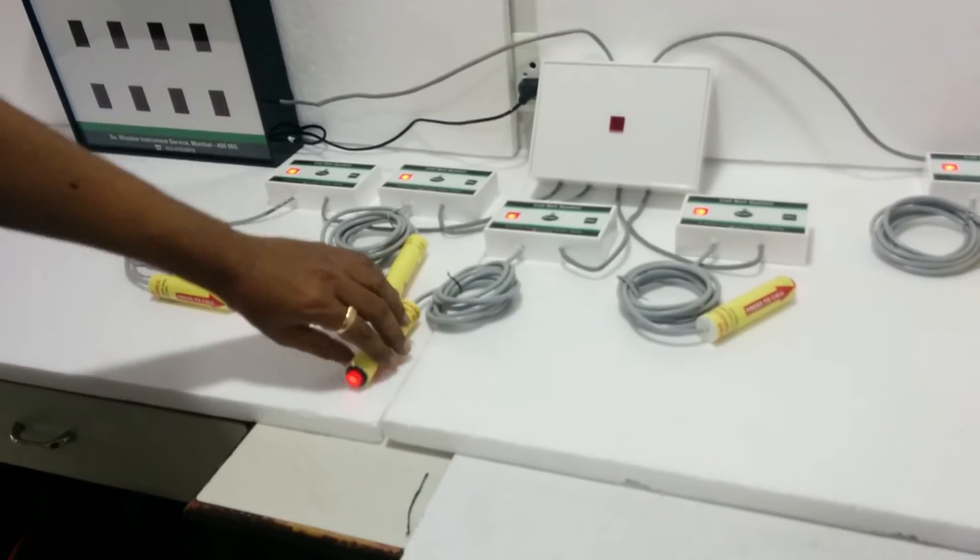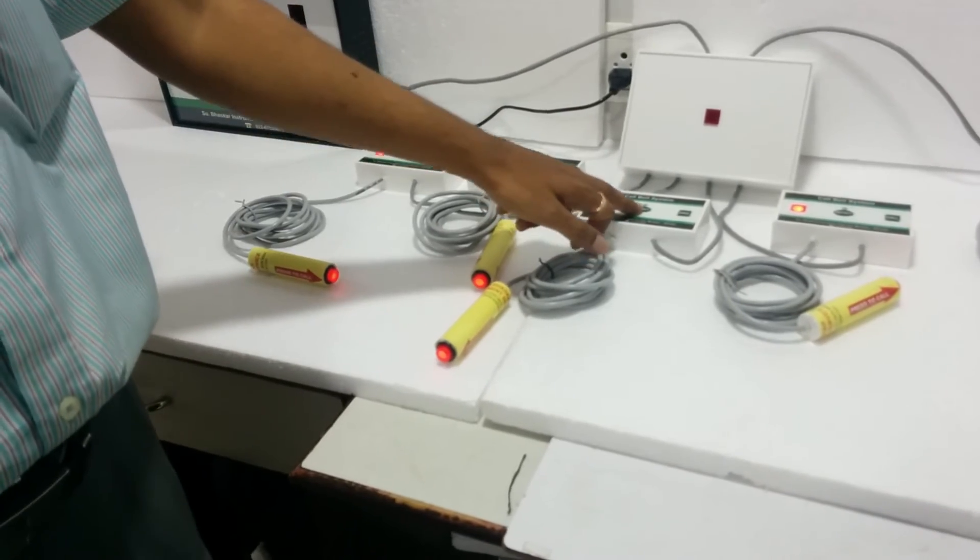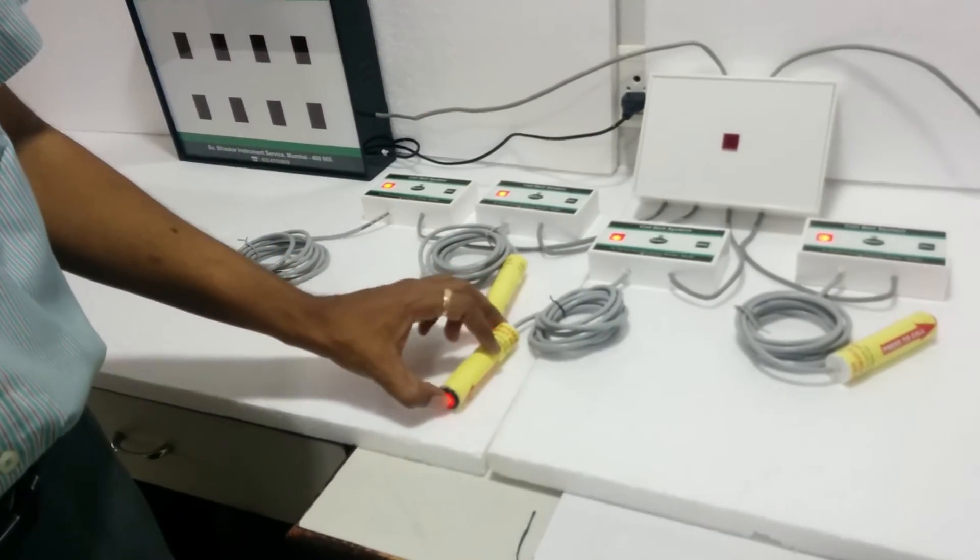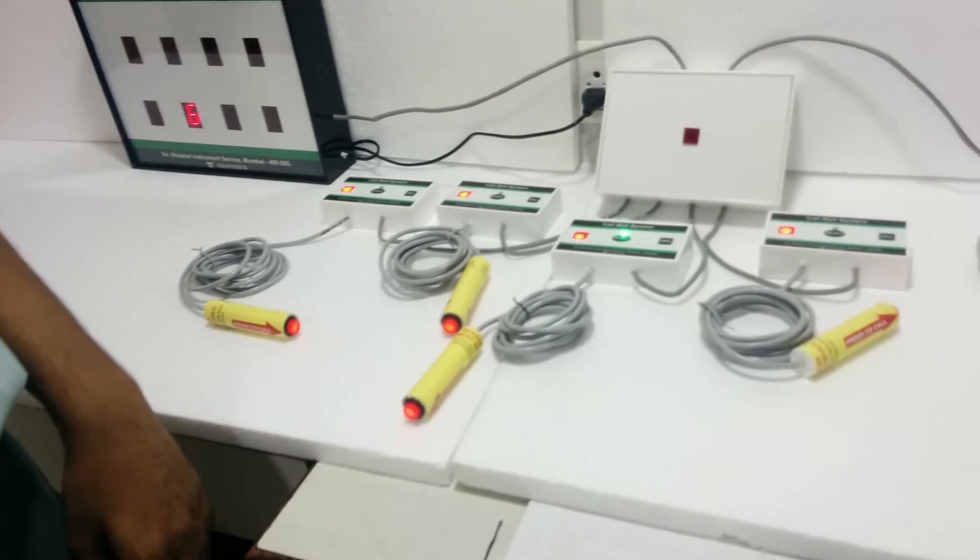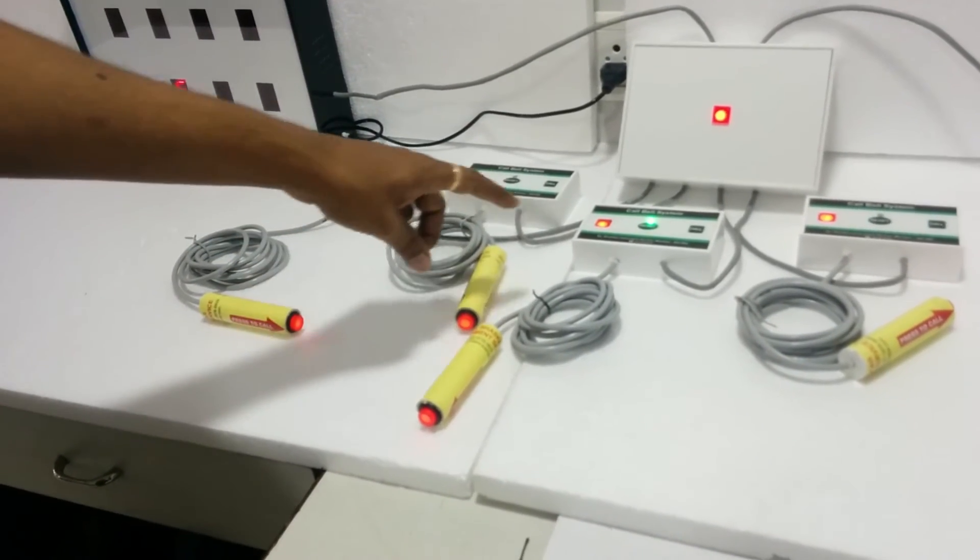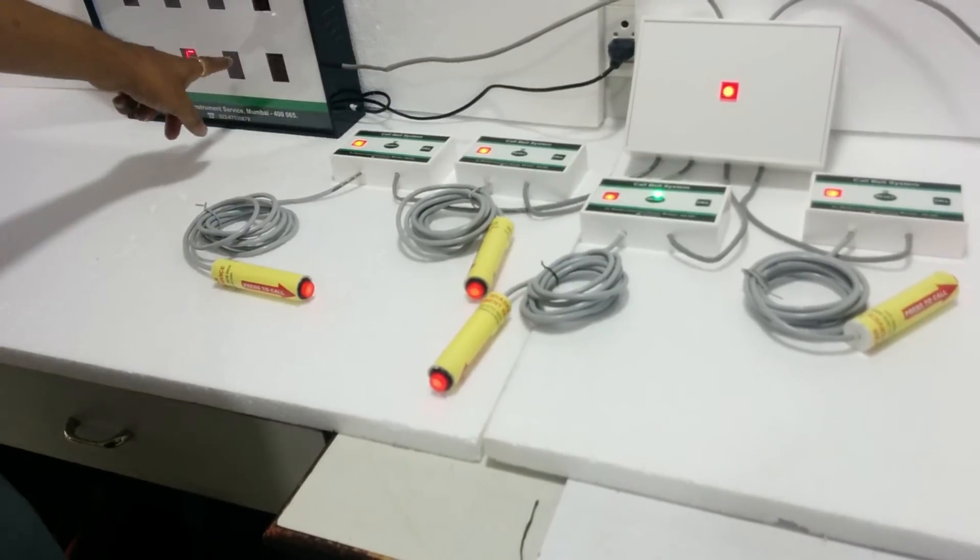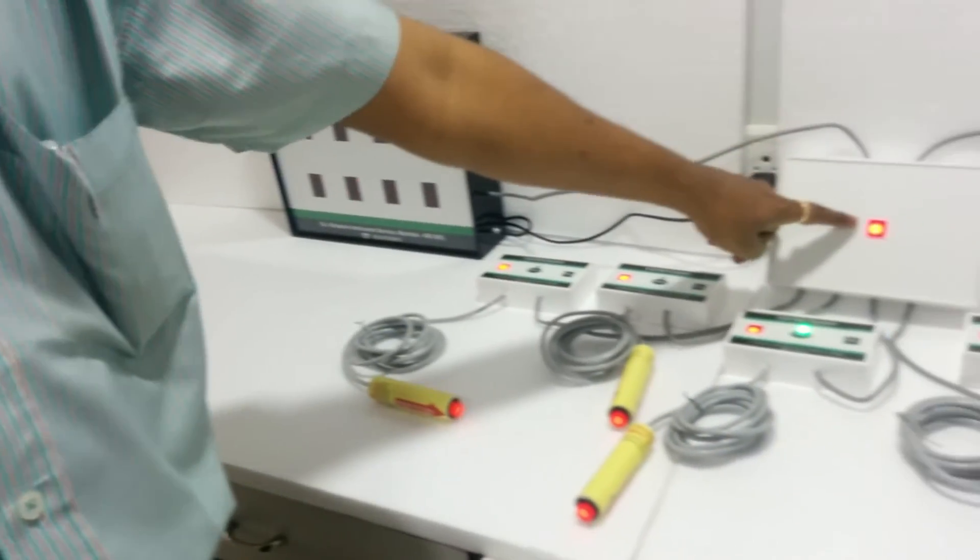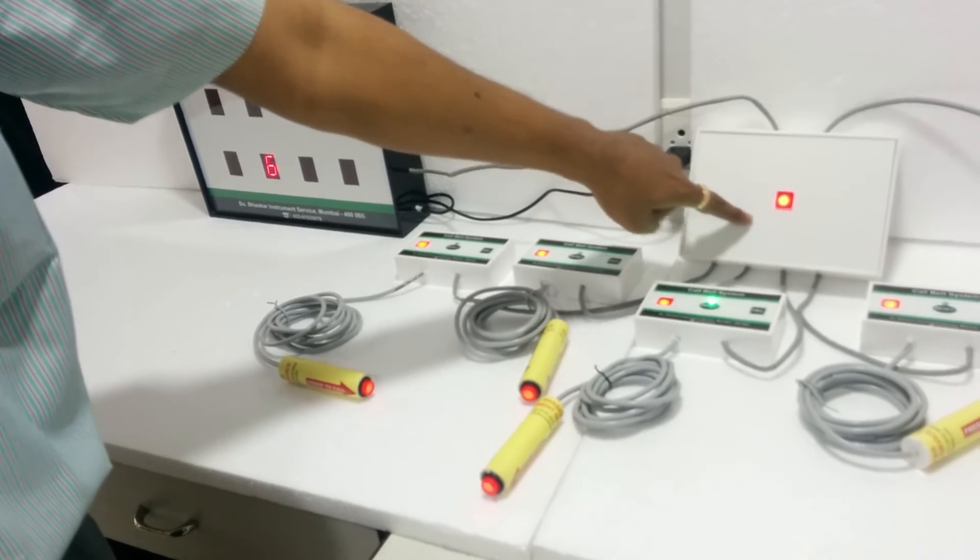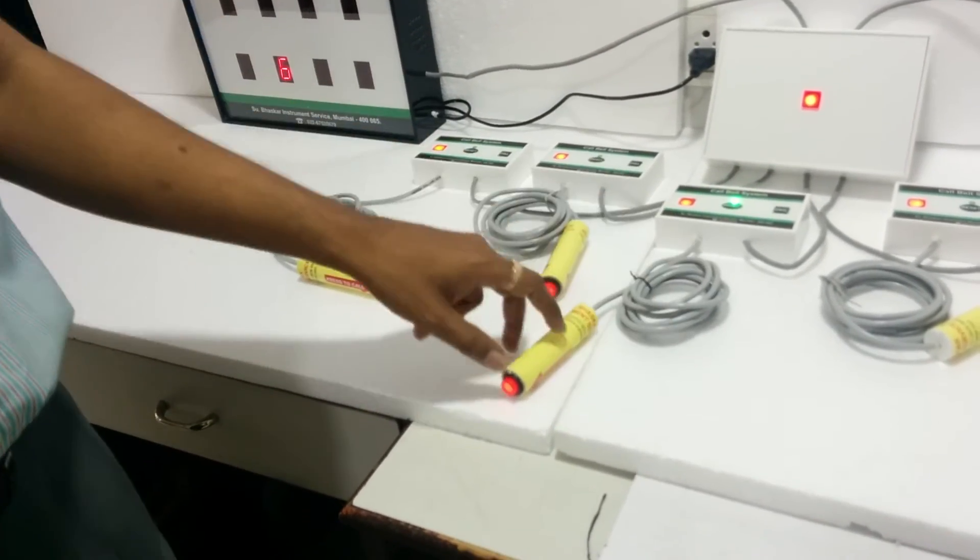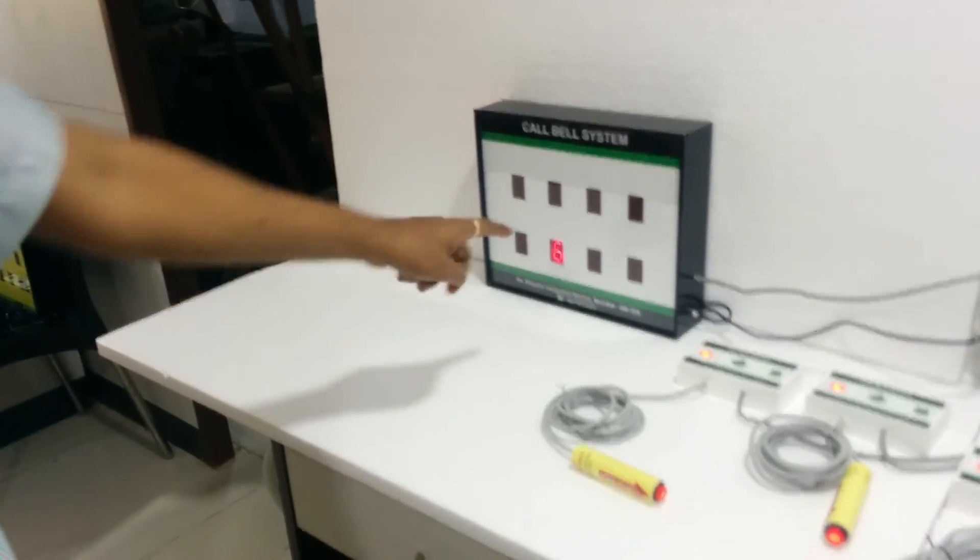If you see, there is a slight delay to switch on this calling light and the ward light. This delay ensures that the call goes to the main panel. The main panel resends the call to the docking station and then it diverts to the bed. It confirms that the call actually displayed on the main panel.